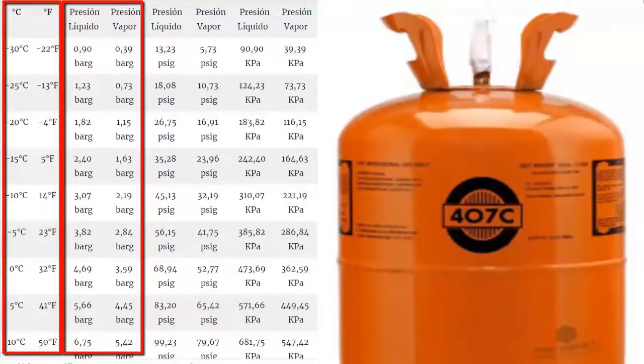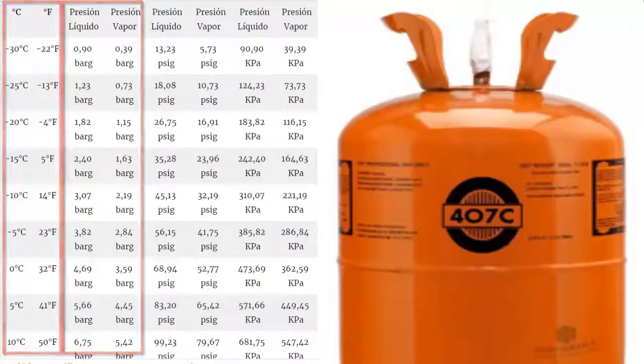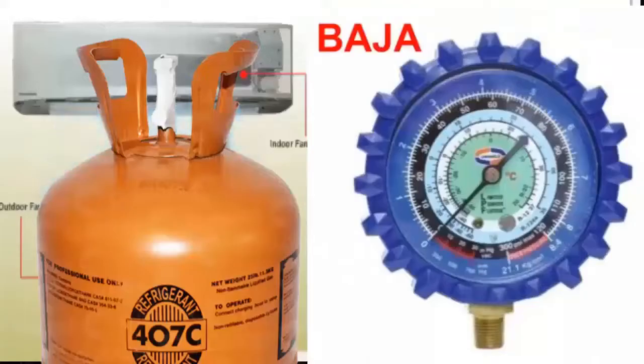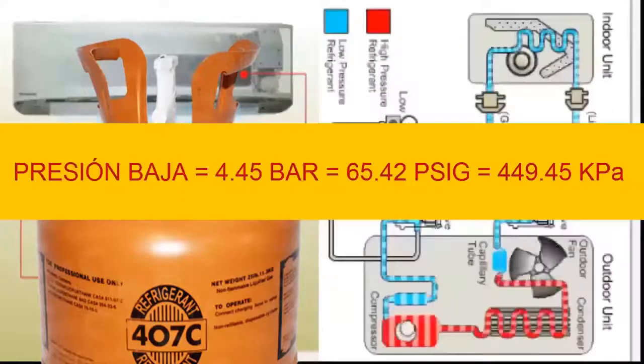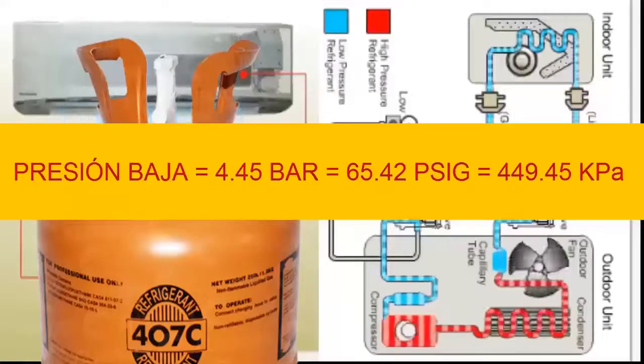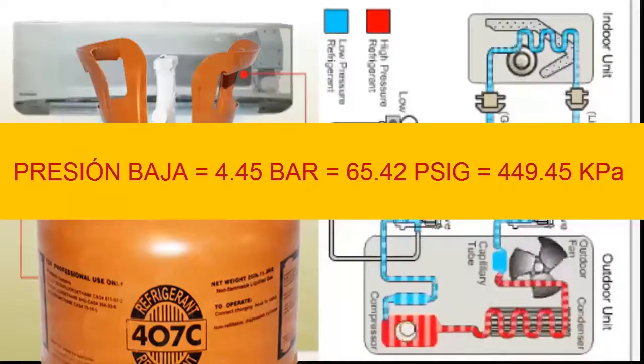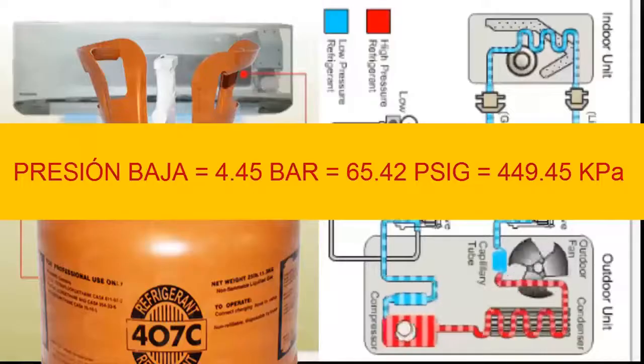Let's look at the most common working pressures, which use vapor pressure as it is the most commonly referenced. To achieve a temperature of 5 degrees Celsius in the evaporator — typical of air conditioning systems, equivalent to 41 degrees Fahrenheit — a low gauge pressure of 4.45 bars is needed, equivalent to 65.42 psi or 449.45 kilopascals.